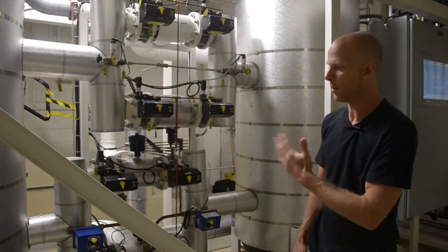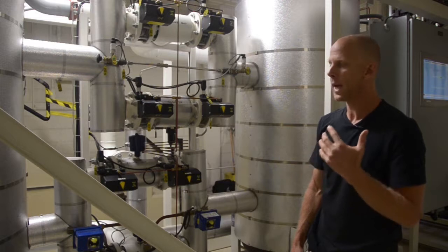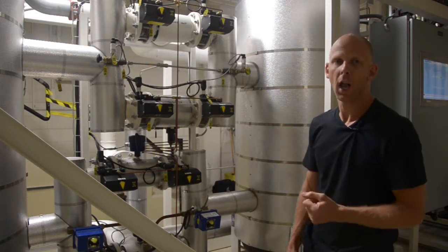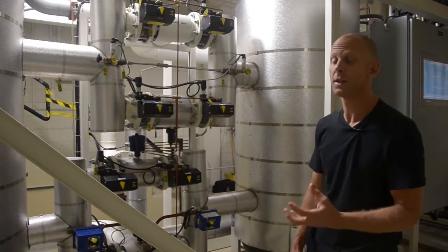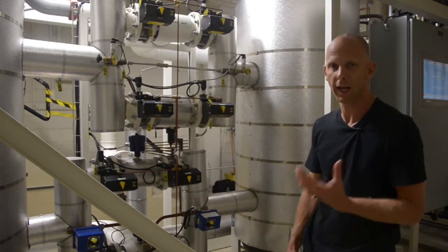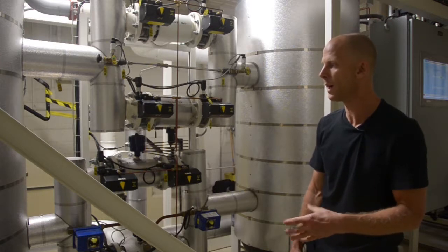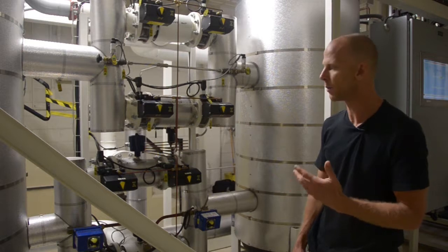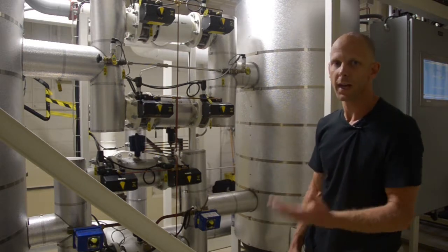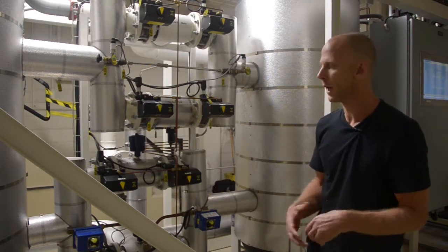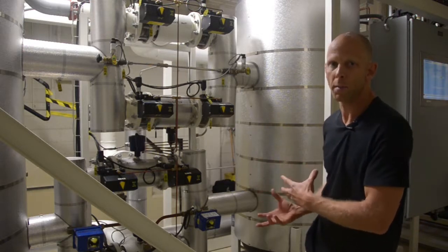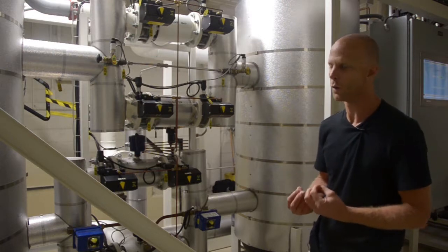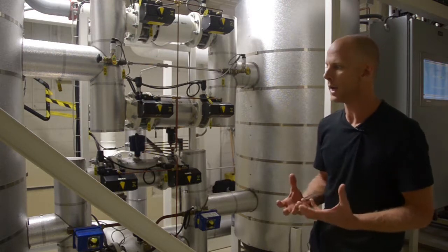Okay, so you'll see that we have two absorber beds. We call it bed A and bed B. At any one time during the running of the plant, one bed will be online. It will be a pressurized bed with the process air stream flowing through it, acting as a molecular sieve, removing the CO2 and water vapor, and the process air moving through that bed and on to our cold box and the distillation process. At the same time, the second bed will be regenerating. After a certain period of acting as an online bed, the molecular sieve material becomes saturated with CO2 and water vapor, and we need to clean the bed.